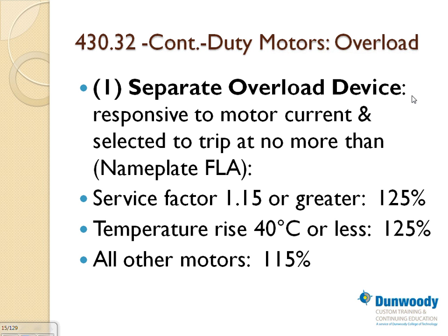Okay, so if you have a motor, and to protect the motor, guys, there are a few things you have to know. If the service factor is 1.15 or greater, or temperature rise as well as all other motors. Service factor 1.15, the way I understand it, if you have a 100 horsepower motor, they allow you 15% extra to overload that motor. Not continuously though. So if that's the situation, then they allow you 25% more on the overload. So if your motor is a 100 amp motor, nameplate, you can set your overload electronically or heater up to 125 amps. So you allow the motor to overload 25%. Why? Because it's designed to be abused and used.